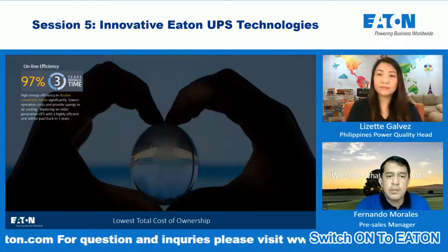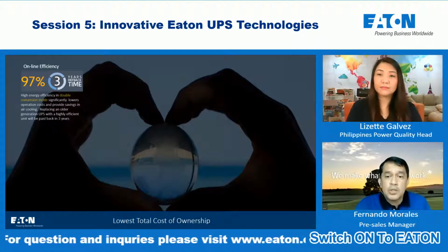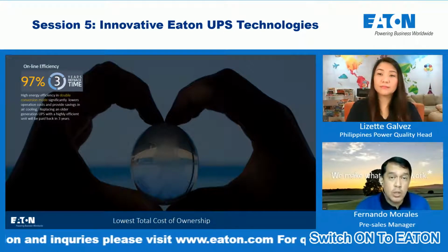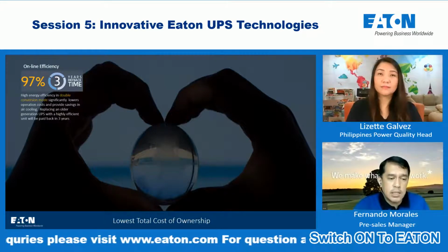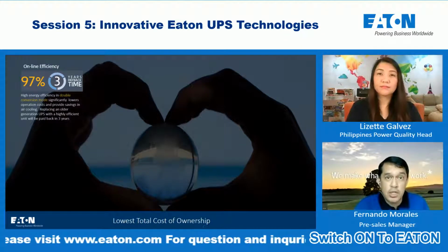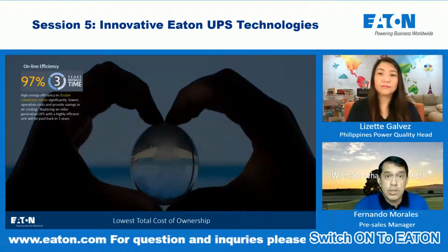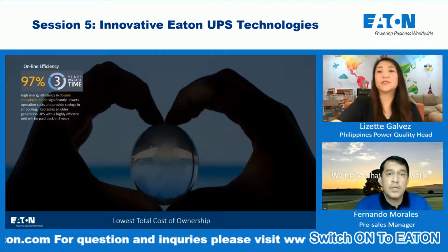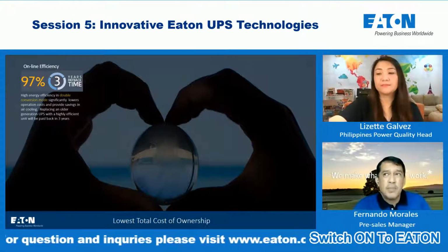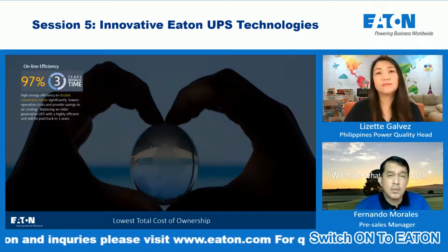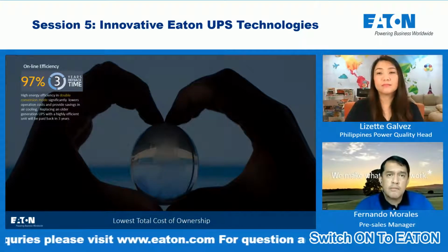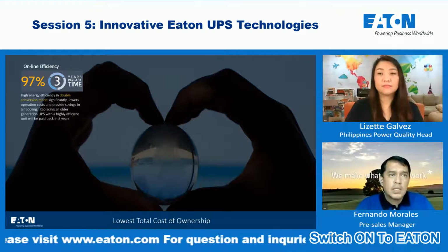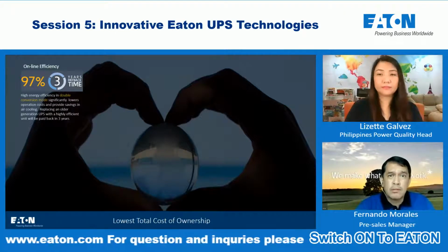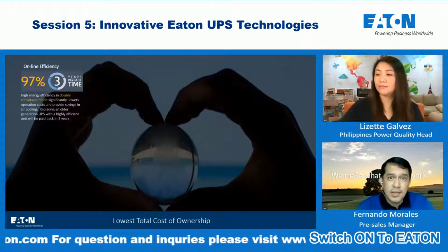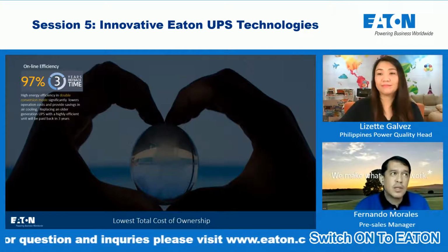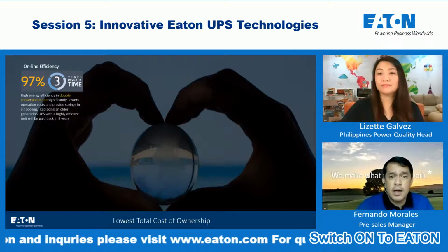The UPS operating efficiency is one of the determining factors in operating expenses. We know that the efficiency of the UPS is proportionate to the amount of load - the higher the load of the UPS, the higher the efficiency we can enjoy. But most of the UPS, especially our installed base in the field, is barely loaded. Some are loaded only 10%, and most are loaded between 20 to 40%.